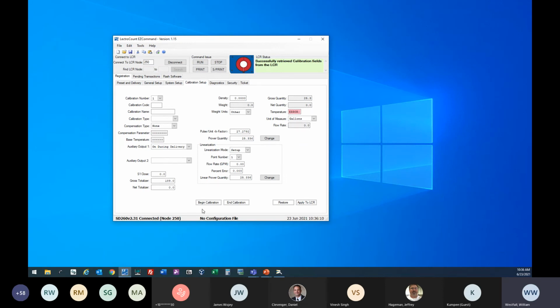So in order to begin a calibration, all we want to do is just go ahead and hit this begin calibration. We should see the counter reset. And now we do have a delivery going on, so you can see that we are counting up. When we're done with the delivery, when our prover is full, we would go ahead and hit the end calibration button down below.